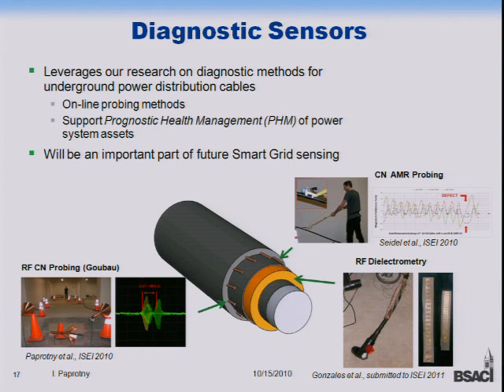What we try to do — and we actually developed some methods in a related project funded by the California Energy Commission — is to measure or probe the integrity of these cables without disconnecting the cable from service. We have some very promising techniques that allow us to detect both the integrity of the concentric neutrals and the integrity of the insulator.